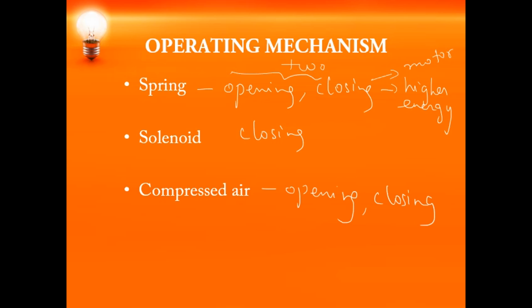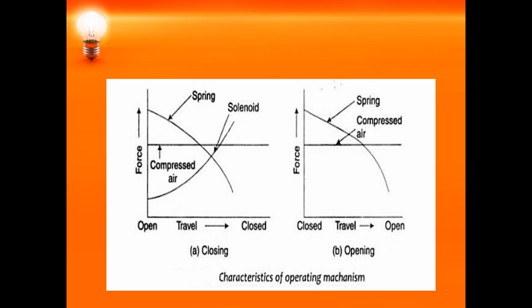Whereas what about compressed air? Compressed air you can use both for closing as well as opening, because its pressure remains almost constant. So these are the characteristics of the operating mechanism during closing and opening. You can see that for the closing operation, the compressed air has a constant force, whereas as we go from the open to the closed position, the spring force decreases, whereas the solenoid force increases. It is the same way for opening. For opening either you go for spring or compressed air, not a solenoid. So this is all about the operating mechanism.